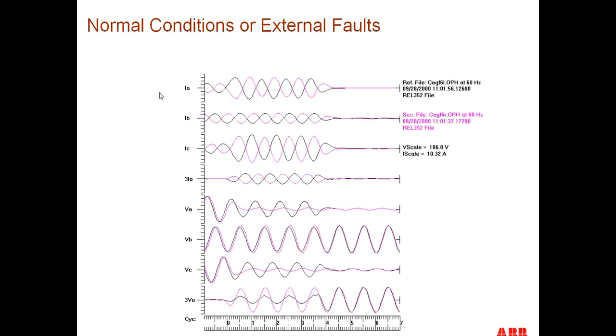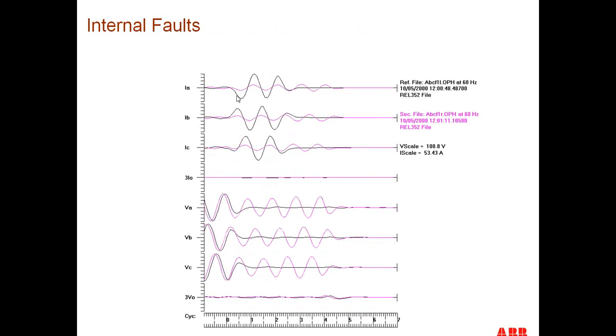Here are a couple of examples. This happens to be for an external fault, where you see the currents are actually out of phase with respect to each other for each of the phases. And for an internal fault, you'll see that it's mainly fed from one contribution from one end, but you can see the currents are more in phase with each other, as you would see on the previous slide.